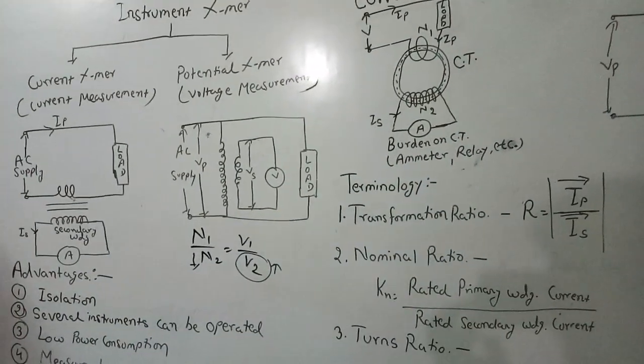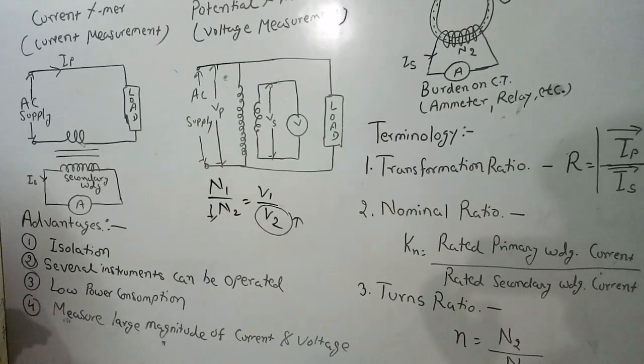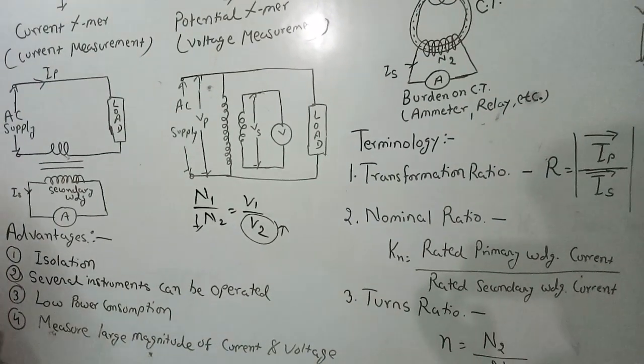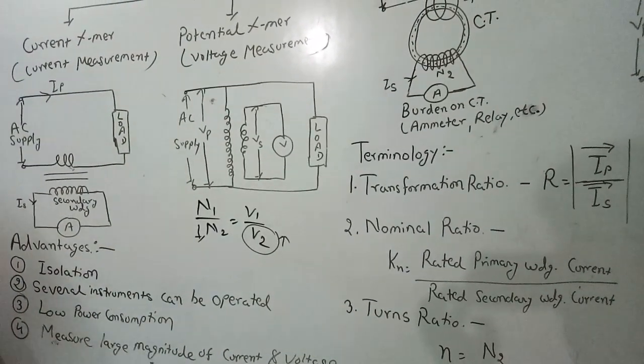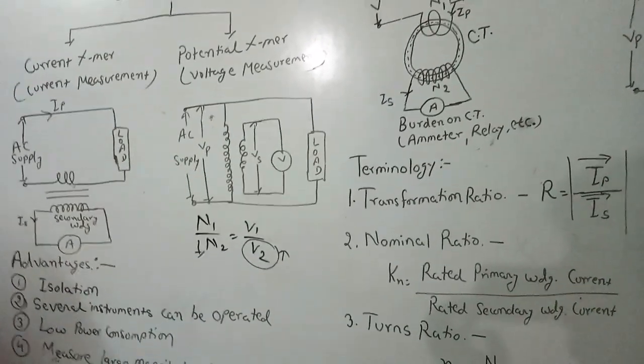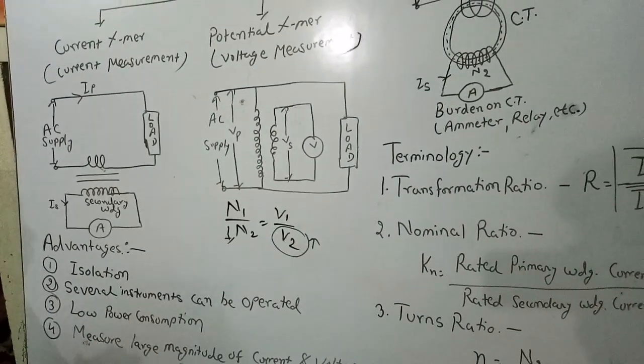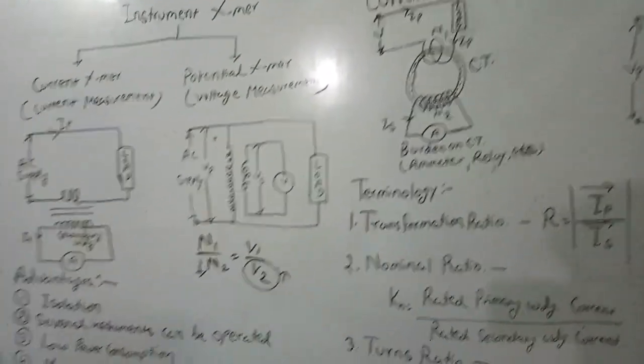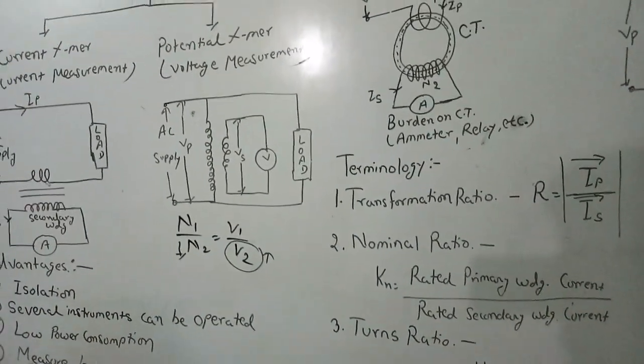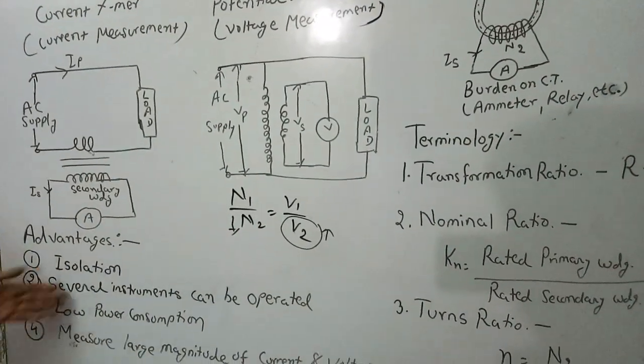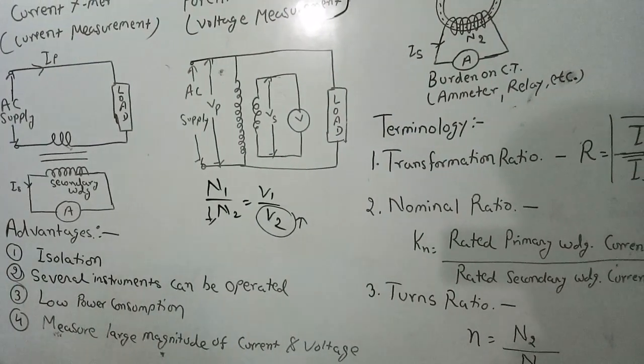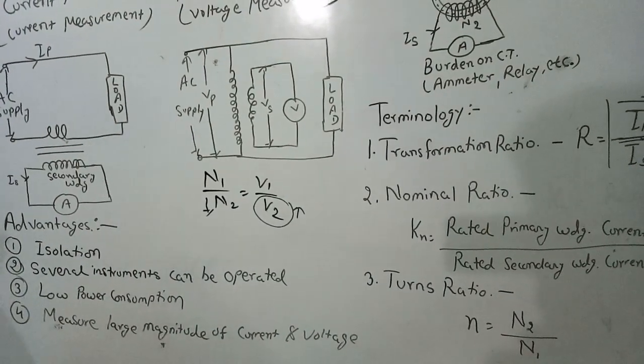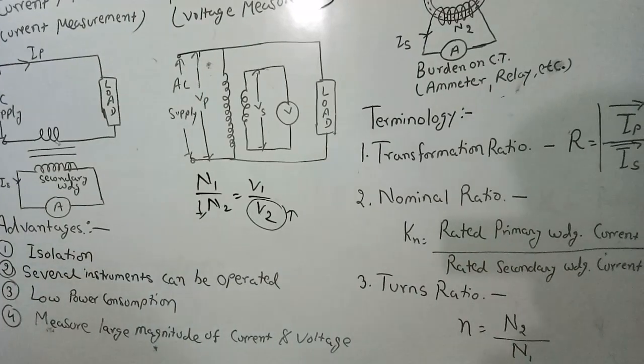Instrument transformers have many advantages. First is isolation — the instrument transformer isolates the load circuit from the source circuit. If we have high voltage on the primary side and low voltage on the secondary side, the transformer is not electrically connected, so it isolates primary and secondary sides protecting personnel working on the secondary side from faults. Second, it can operate several instruments with a single instrument transformer. It also has low power consumption due to very high efficiency, and it measures large magnitudes of voltage and current.